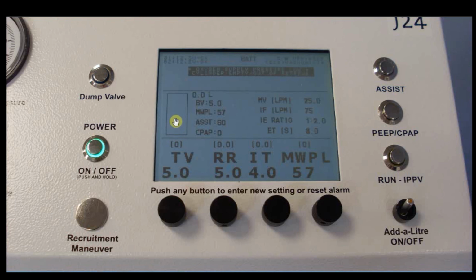The way this works is that when you're ventilating a patient, and if you're getting down to the lower regions of a litre or less, then the machine will automatically add extra oxygen to stop the cylinder running out of gas. If you push the switch to the lower position, switch it down, then it's off and that feature is disabled.